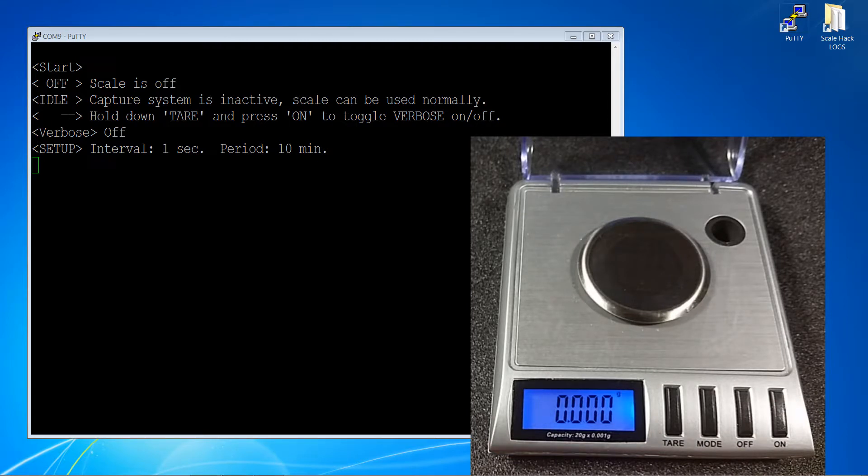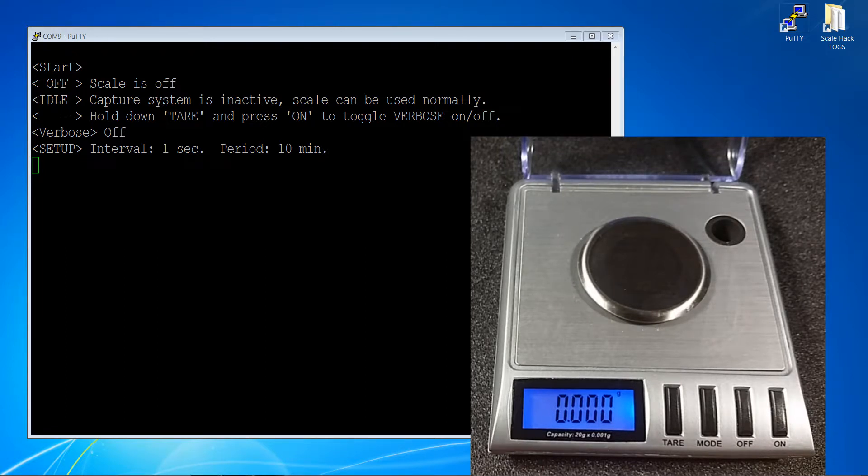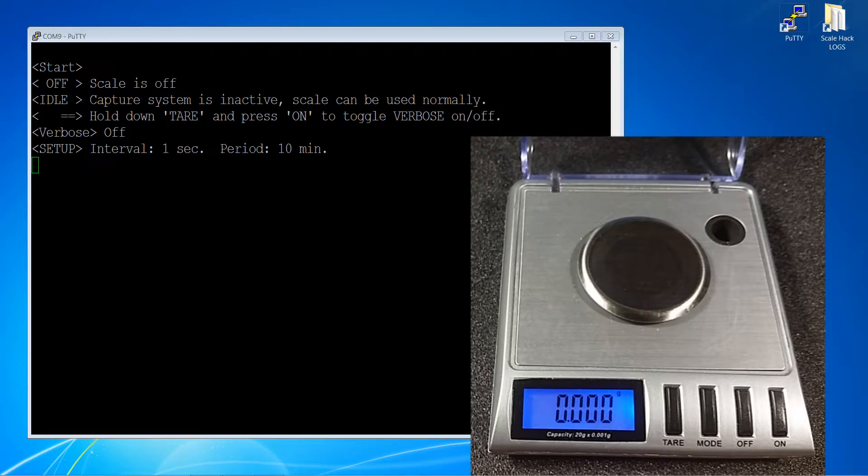This sequence is set to run every 60 seconds. It should be noted that the units will always settle to grams. This has been chosen since it offers the best resolution and also minimal impact on reading variations due to the keep-alive sequence. Details of this are available in the documentation.